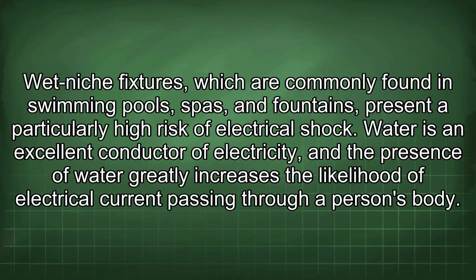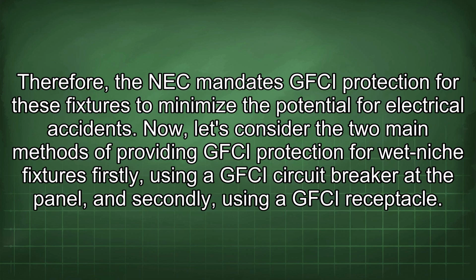Wet niche fixtures, which are commonly found in swimming pools, spas, and fountains, present a particularly high risk of electrical shock. Water is an excellent conductor of electricity, and the presence of water greatly increases the likelihood of electrical current passing through a person's body. Therefore, the NEC mandates GFCI protection for these fixtures to minimize the potential for electrical accidents. Now, let's consider the two main methods of providing GFCI protection for wet niche fixtures. Firstly, using a GFCI circuit breaker at the panel, and secondly, using a GFCI receptacle.